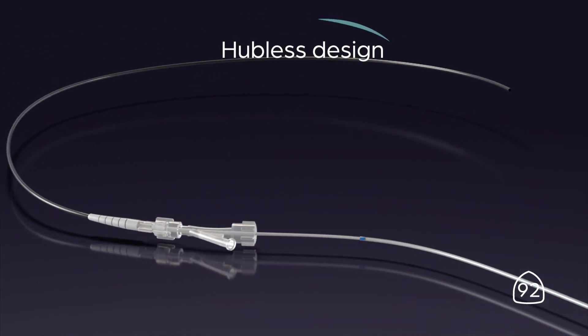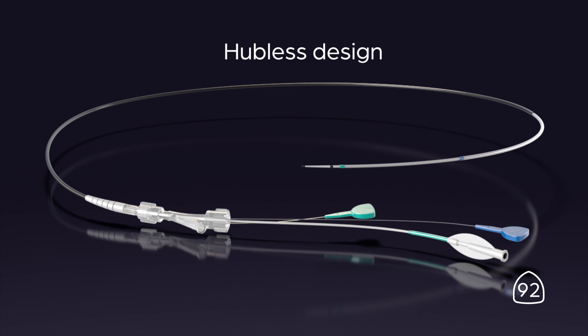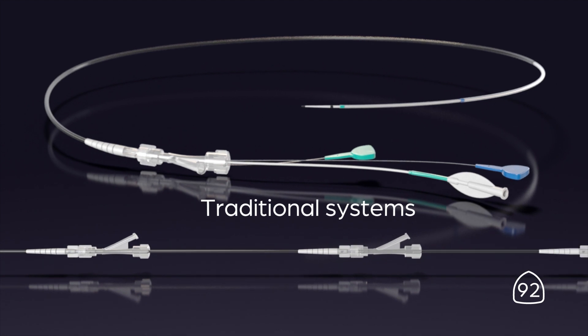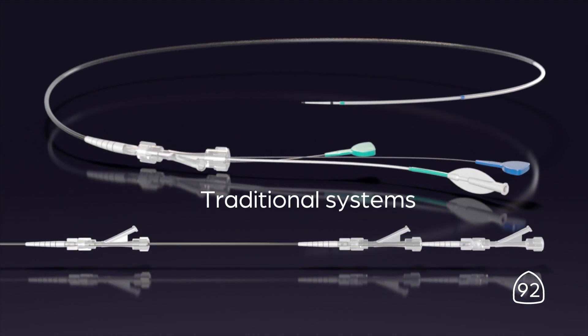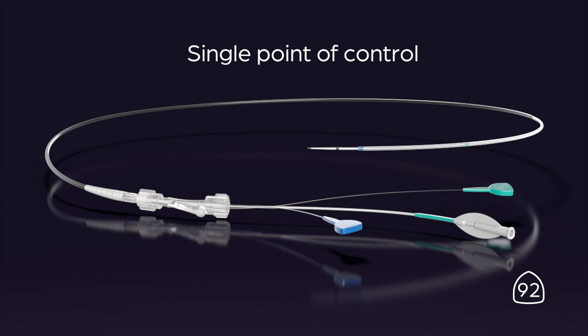The Mono Point platform is designed to nest each component inside the next. This hubless design enables you to use the full length of the High Point aspiration catheters even when telescoping to go further, whereas traditional multi-axial systems suffer from hubbing out with rotating hemostatic valves. Advancing from a single point of control, the system is engineered to work as one cohesive unit, and each component can be managed independently or together.